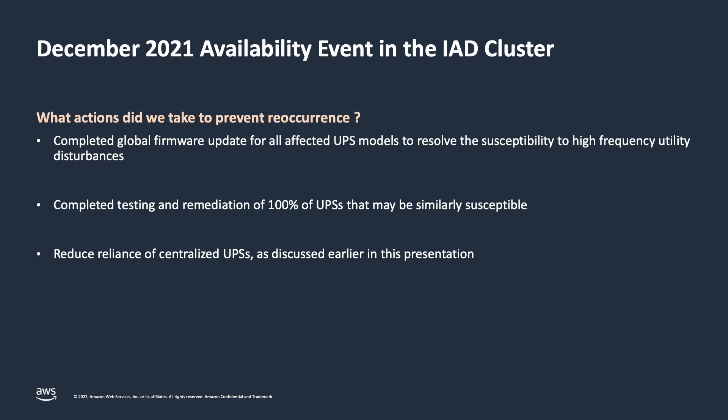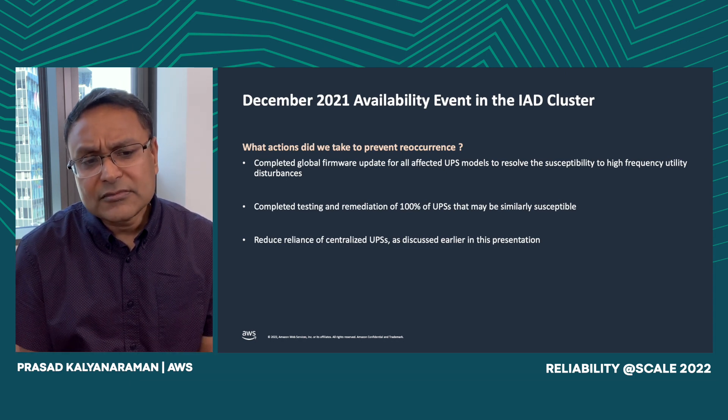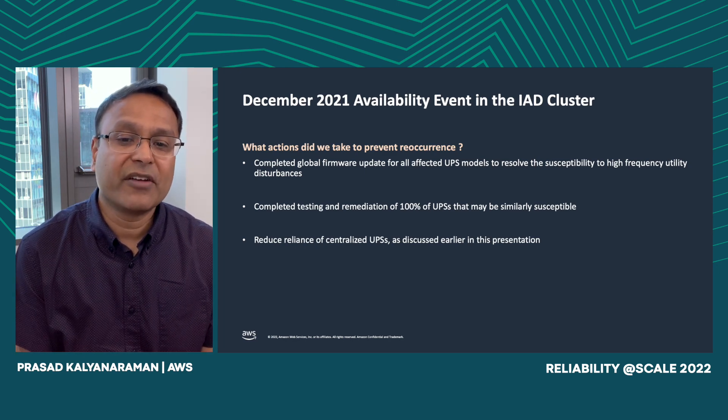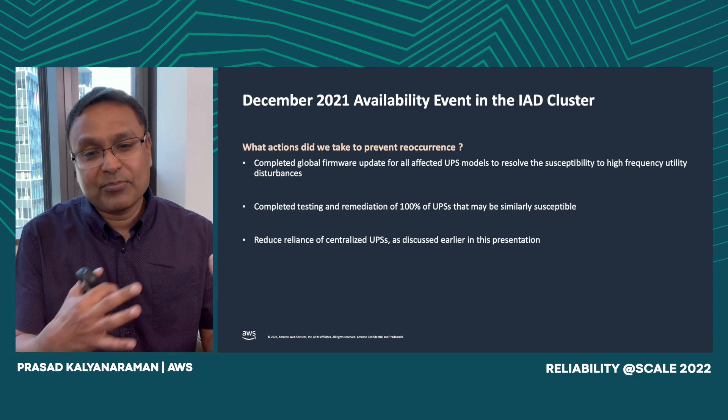We also tested and remediated 100% of the UPSs across the entire fleet that were similarly susceptible. And we've moved away from the centralized UPS design to one with battery backup units on individual servers, which helps with blast radius. To recap our evolution: we started with N plus C, realized maintenance reduced our redundancy so we moved to N plus 2C, then eliminated large-blast-radius centralized UPSs to ensure redundancy across the entire lineup. Then we built self-healing systems so that when excursions happen we can automatically heal, and we automated that process.